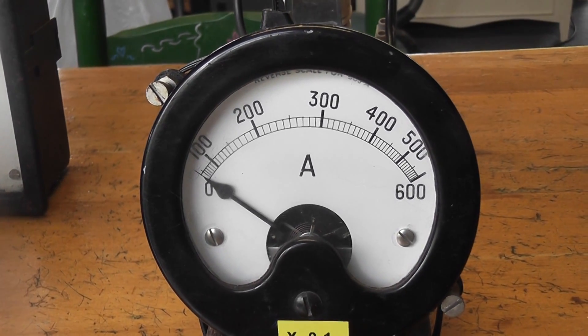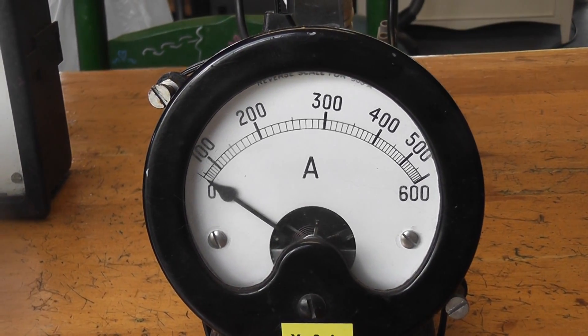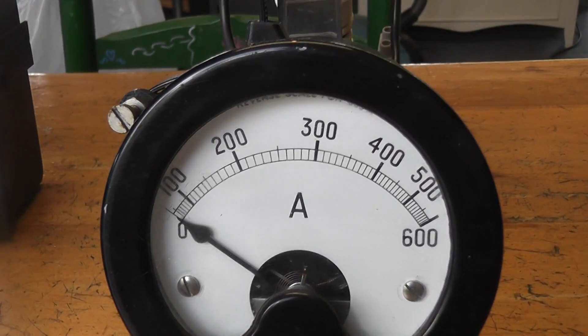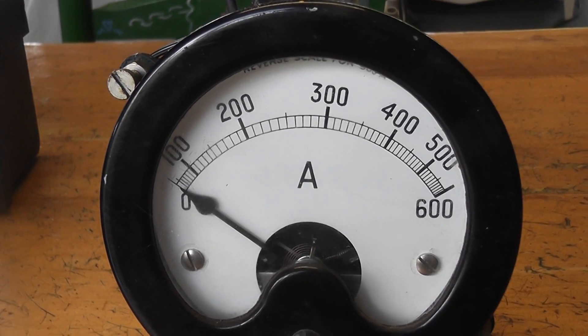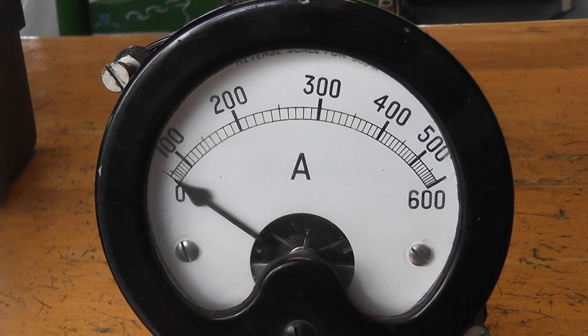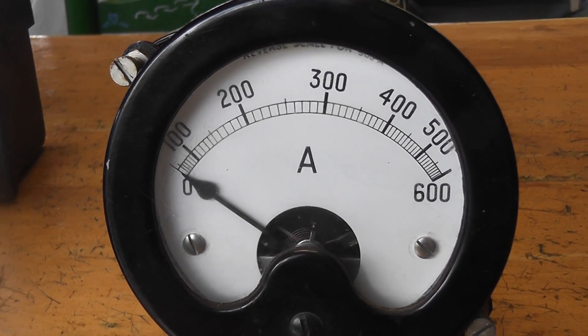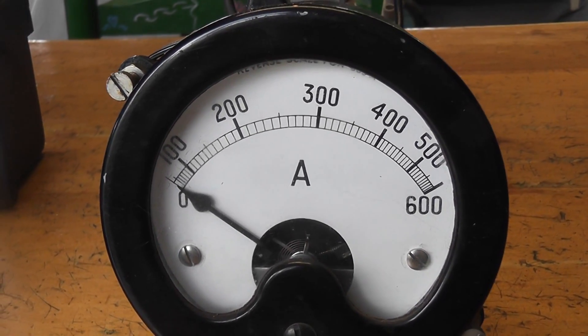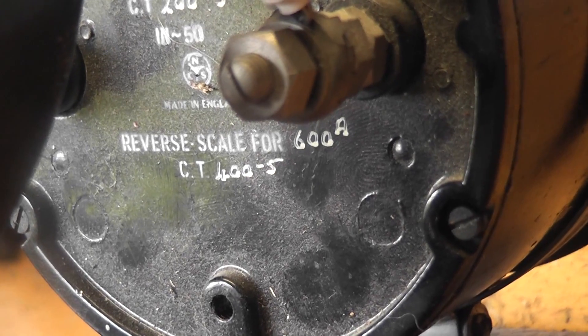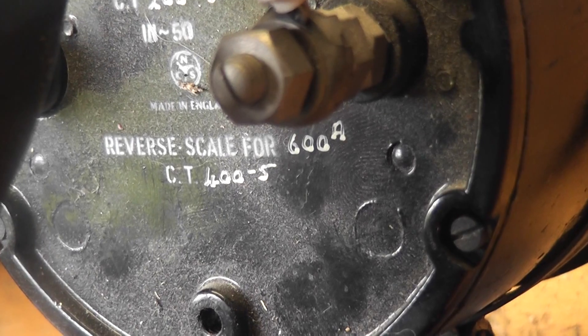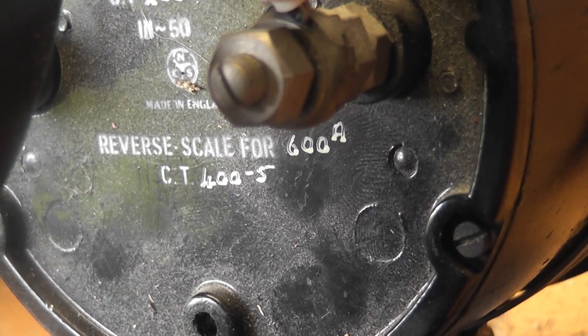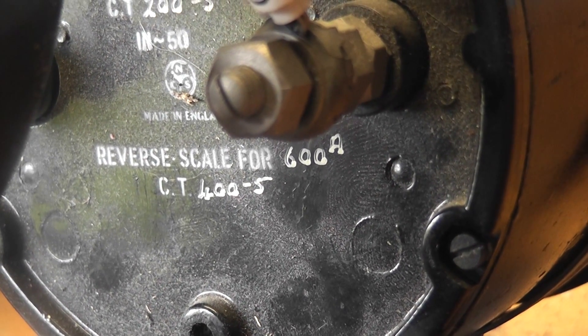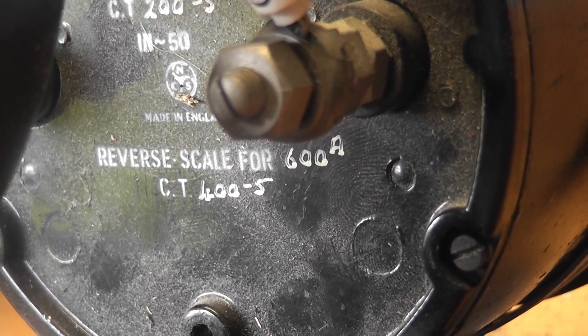This meter goes up to 600 ampere but the actual scale is set for 400 to 5 which is marked on the back of the meter. Nameplate ratings are often marked either on the back of the meter or on the nameplate at the front itself.